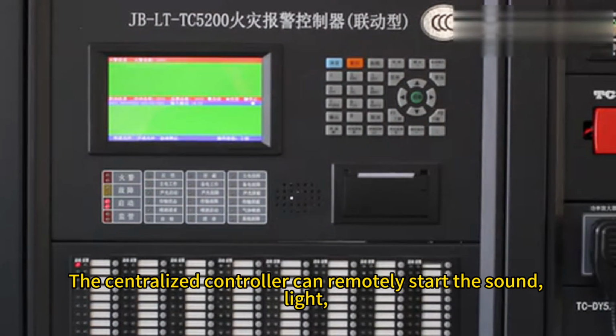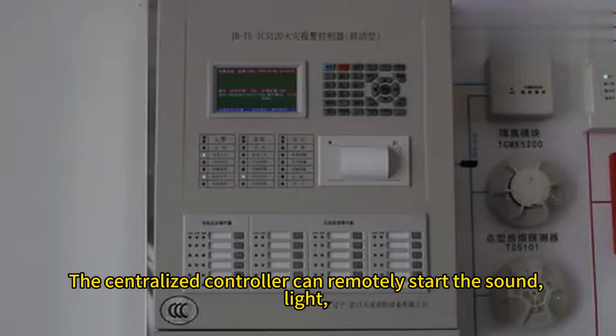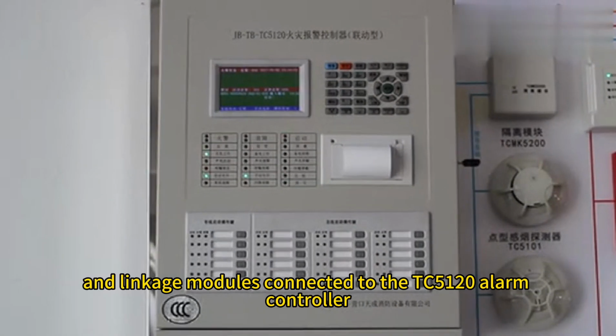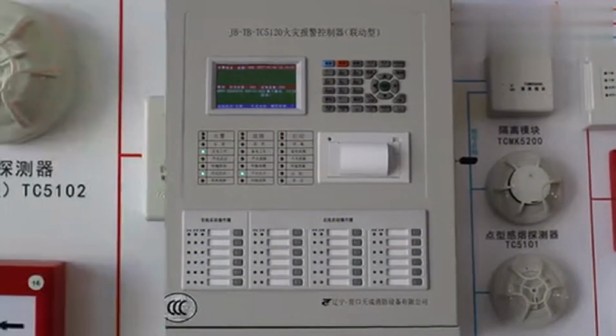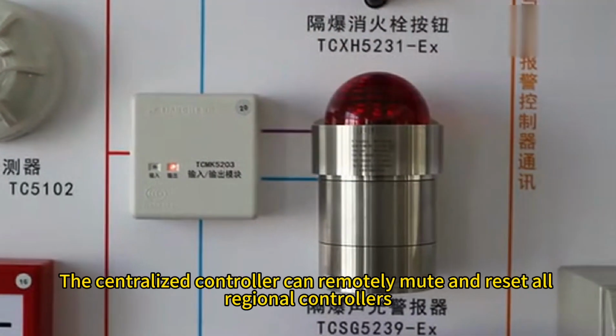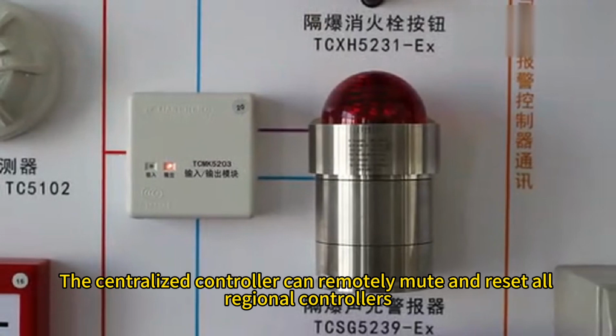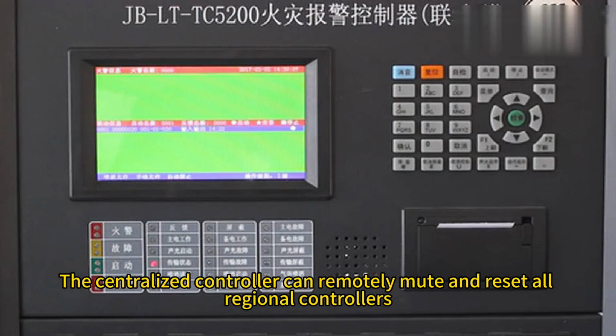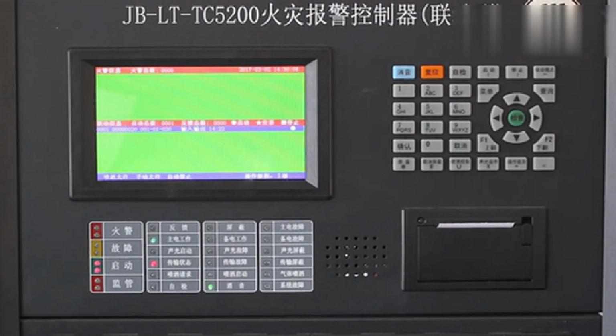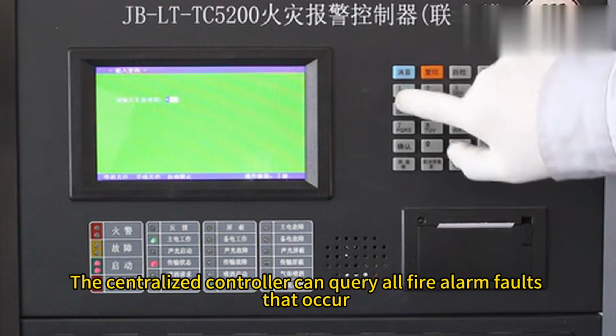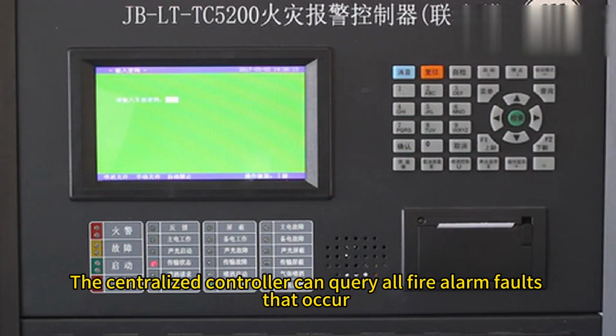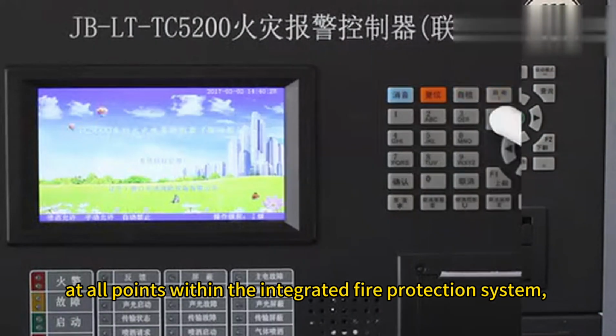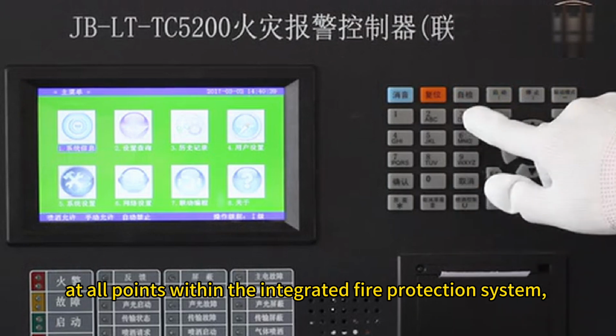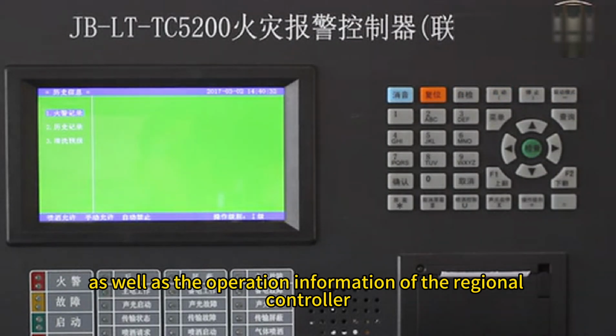The centralized controller can remotely start the sound, light, and linkage modules connected to the TC5120 alarm controller. The centralized controller can remotely mute and reset all regional controllers. The centralized controller can query all fire alarm faults that occur at all points within the integrated fire protection system, as well as the operation information of the regional controller.